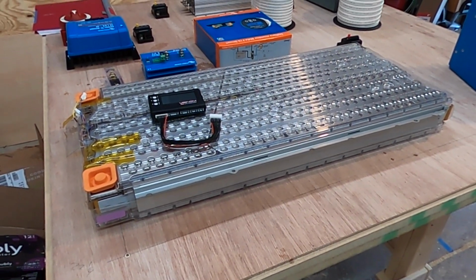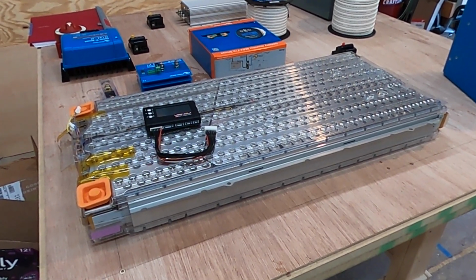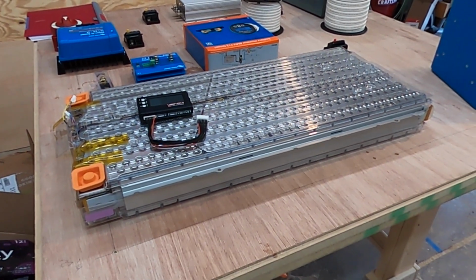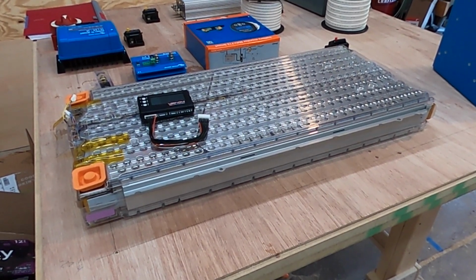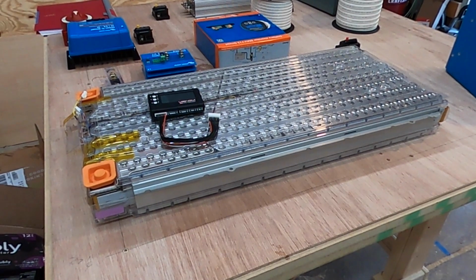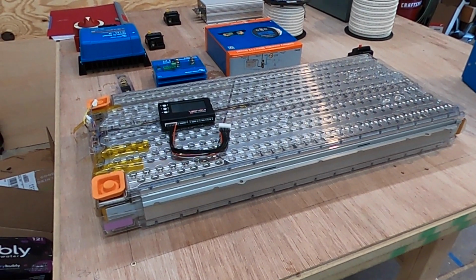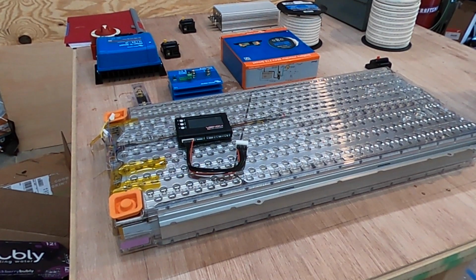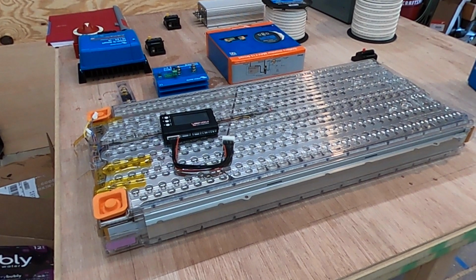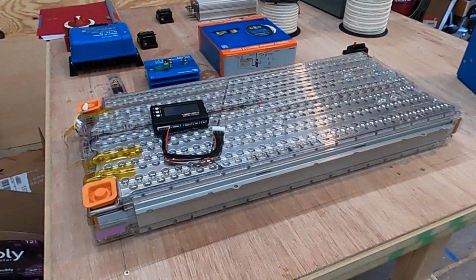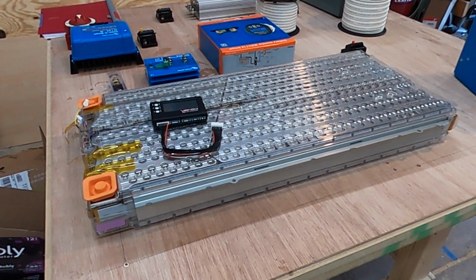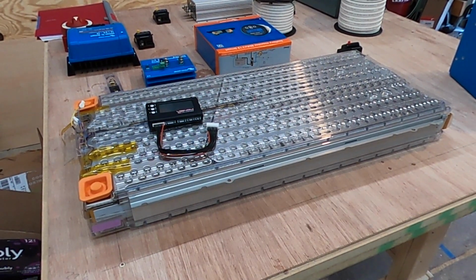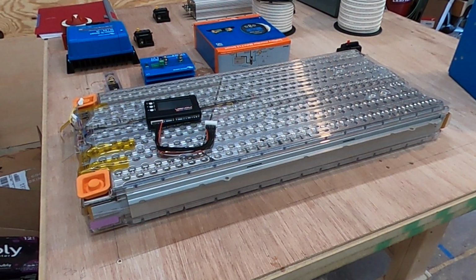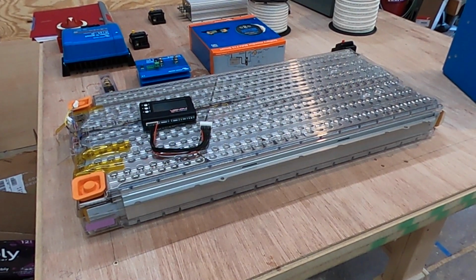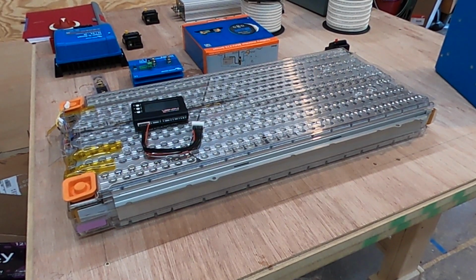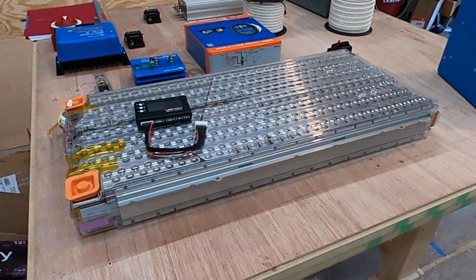Another thing to be conscious of is you're not supposed to charge or discharge a Tesla battery module if it gets below freezing. The charge rate needs to be slowed as you approach about 45 degrees Fahrenheit. These requirements are why we chose Victron components - they're configurable, so you can set the charge rate to adjust for lithium-ion batteries. There's a temperature input that goes into our inverter charger and across the VE bus, which connects the different components together, letting the inverter charger know it needs to change its charge rate or stop charging below a critical temperature. This same logic is used on the DC to DC charger and the charge controller, so we have to worry less about charging components. The inverter charger is also smart enough to set a voltage disconnect, stopping discharge at a certain voltage.